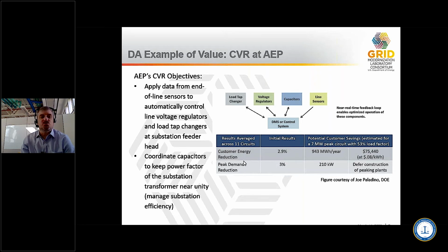What they did was apply data from end-of-line sensors, extra sensors added to the system to see what the voltage was far out on the circuit, at the end of it. This added extra visibility to the system, to see whether they could get enough benefit out of those systems to pay for the end-of-line sensors while also benefiting their customers. Using those sensors, they coordinated capacitor operations to keep the power factor at the substation near unity, managing substation efficiency.